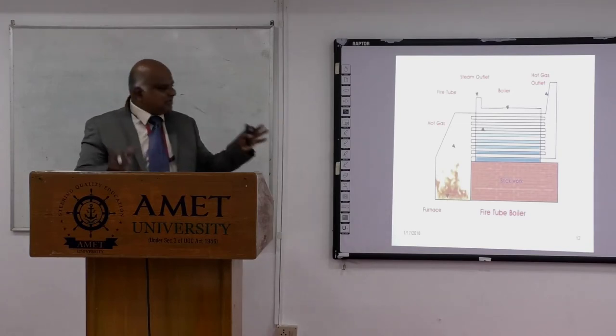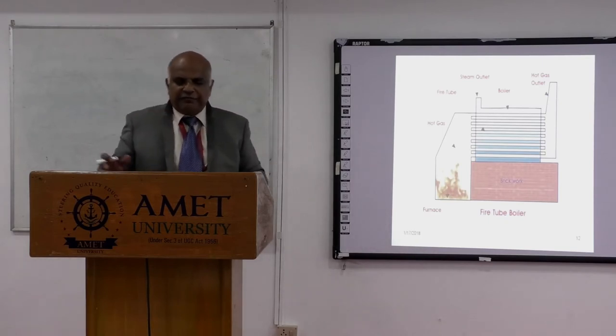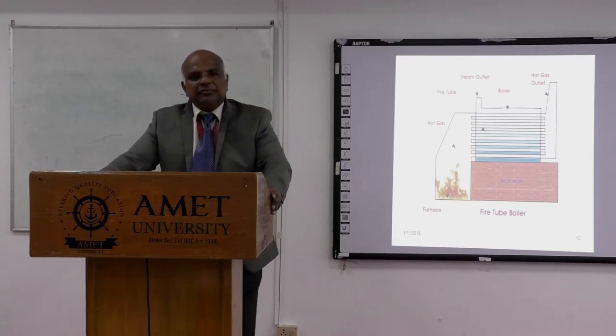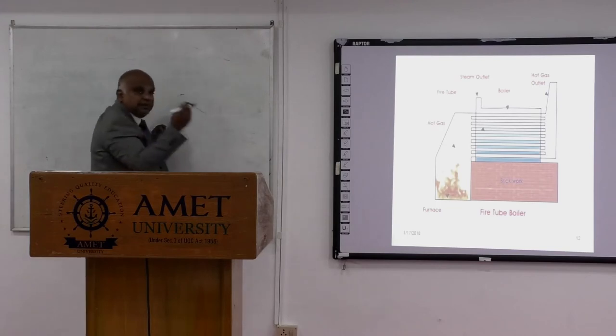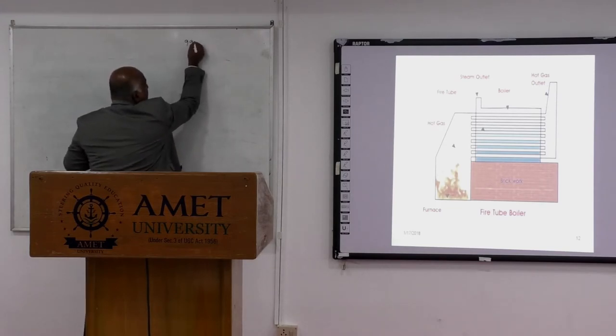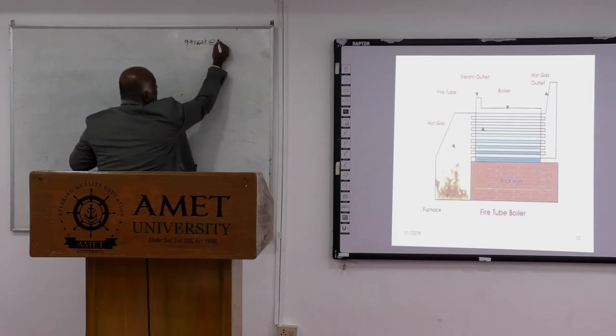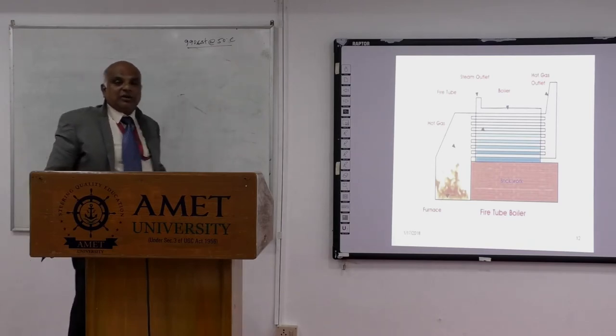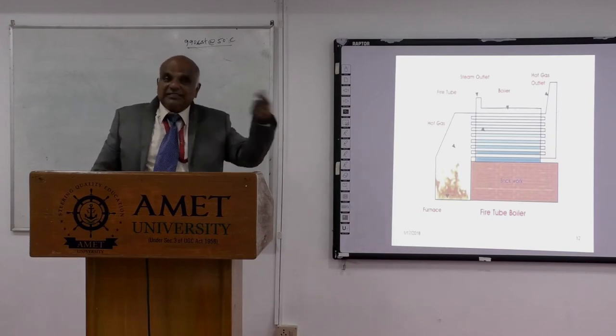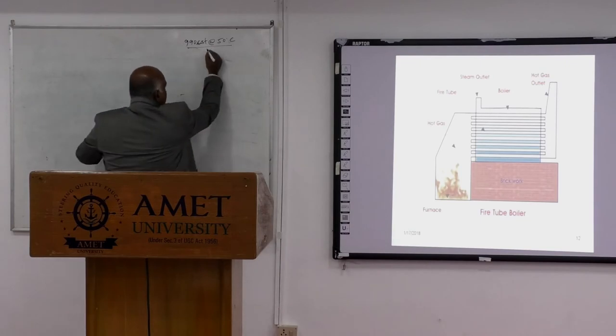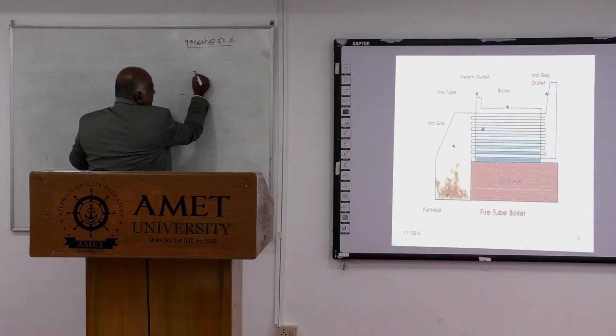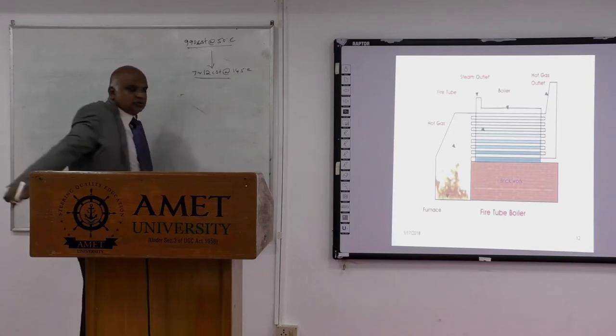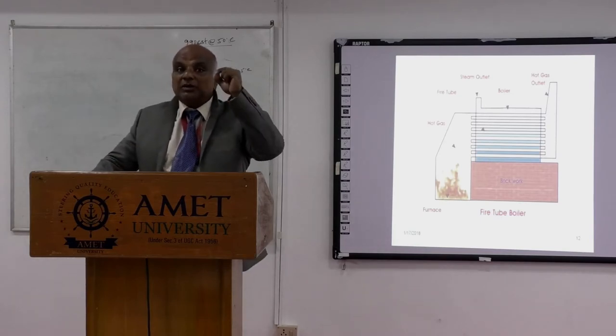Where is a boiler used on a ship? On a motor ship, we need a boiler because the bunkers received come at 990 CST viscosity at 50 degrees centigrade. We cannot use this oil directly in the internal combustion engine. We have to heat it up and bring the viscosity down to between 7 to 12 CST at approximately 125 degrees centigrade, then send it through the fuel injector.